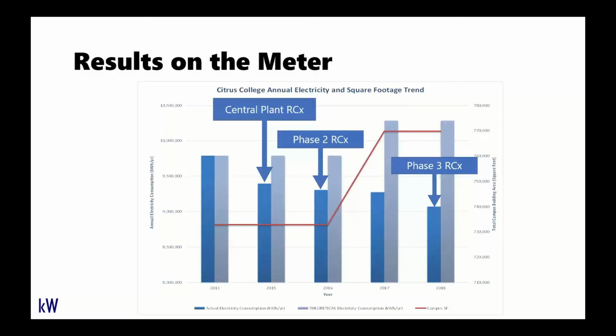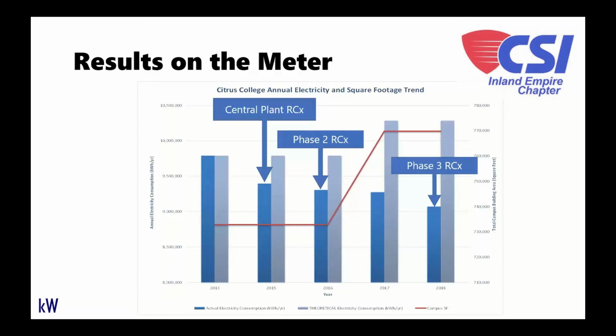And I was talking to Fred the other day, and he mentioned that I believe you said there was like a 10 or 15% increase in your electric rates over the same time frame. And despite that increase in rates, you have not experienced an increase in your total energy cost, in part due to these continued reductions of retro commissioning that you've been... That's correct... over the years. So really great way to keep costs in line, prevent creep of energy costs over time. And if you are looking at your energy data and you see that number going up and up and up over the years, then that's a really good indicator that retro commissioning might be for you.